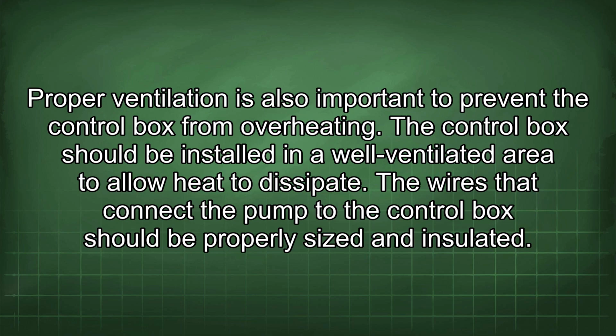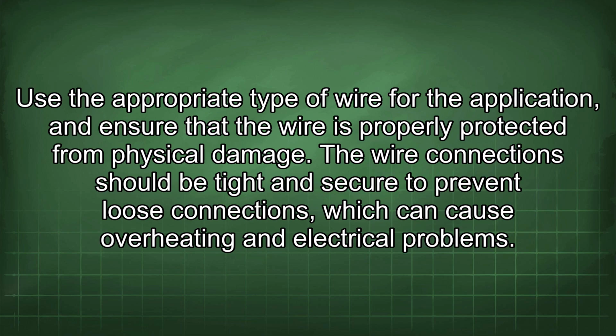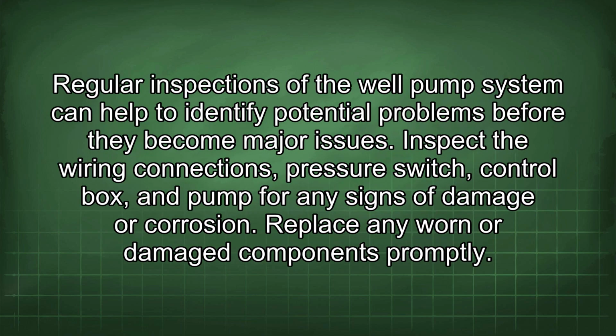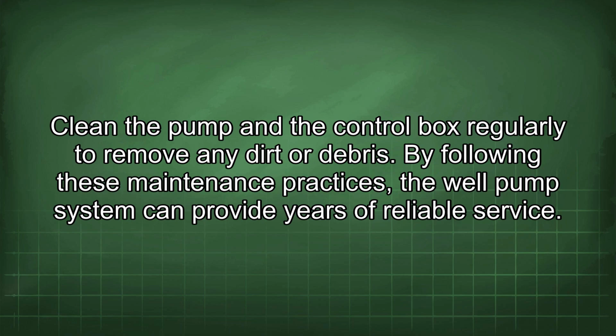The wires that connect the pump to the control box should be properly sized and insulated. Use the appropriate type of wire for the application and ensure that the wire is properly protected from physical damage. The wire connections should be tight and secure to prevent loose connections, which can cause overheating and electrical problems. Regular inspections of the well pump system can help to identify potential problems before they become major issues. Inspect the wiring connections, pressure switch, control box, and pump for any signs of damage or corrosion. Replace any worn or damaged components promptly. Clean the pump and the control box regularly to remove any dirt or debris. By following these maintenance practices, the well pump system can provide years of reliable service.